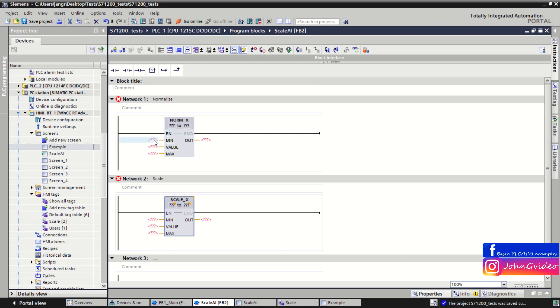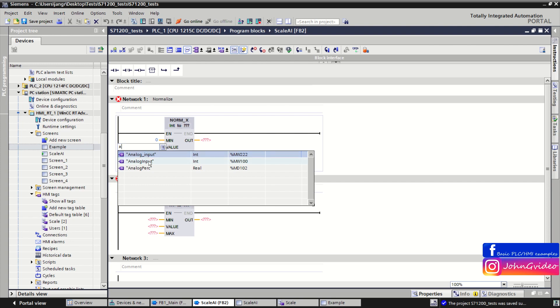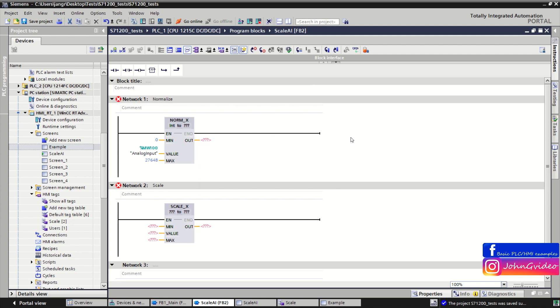On the MIN input we insert the low limit of the value range — for us this is 0. On the MAX input we insert the high limit of the value range — for us this is 27648. On the VALUE input we insert the value which we want to normalize, so for example it is the analog input from our analog input card.